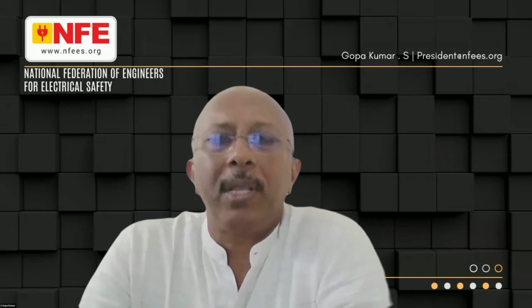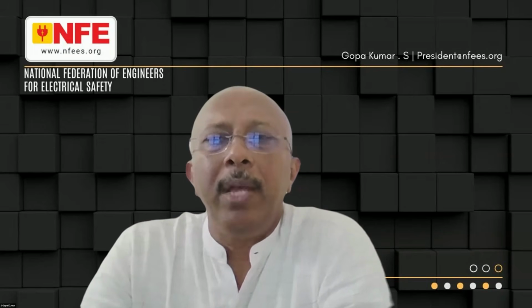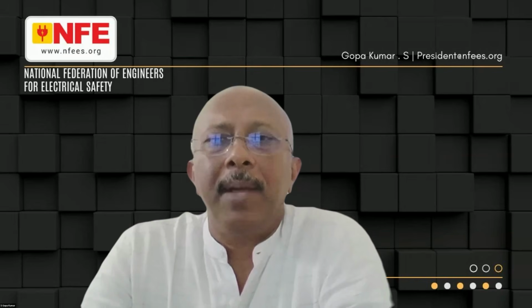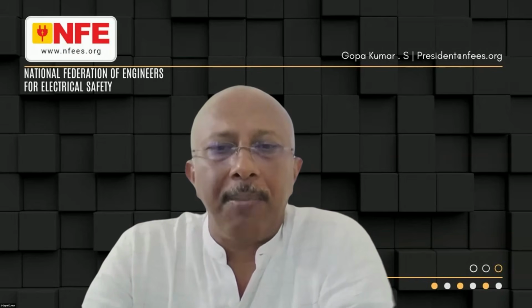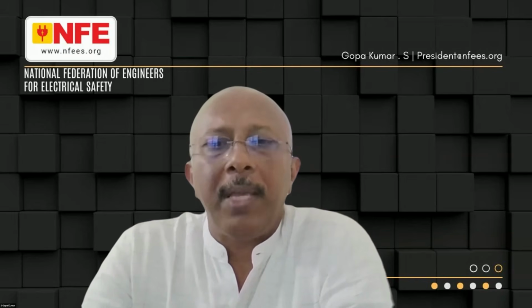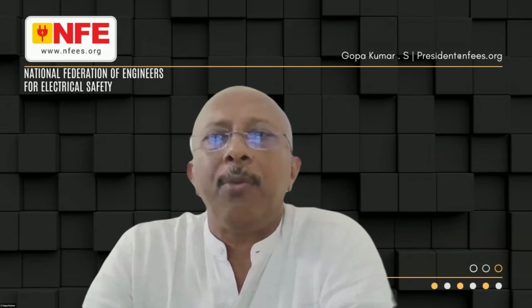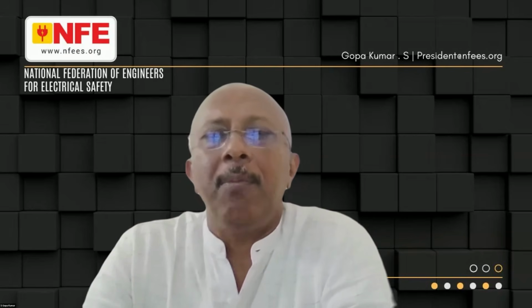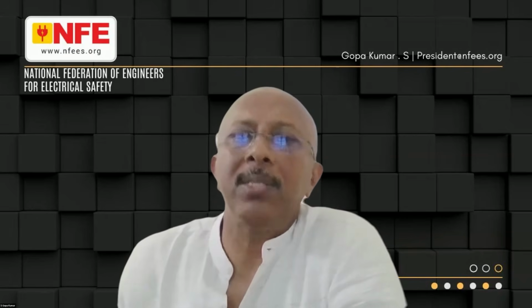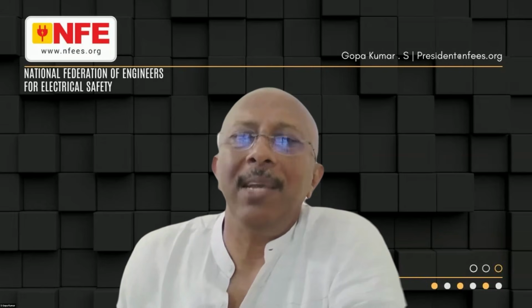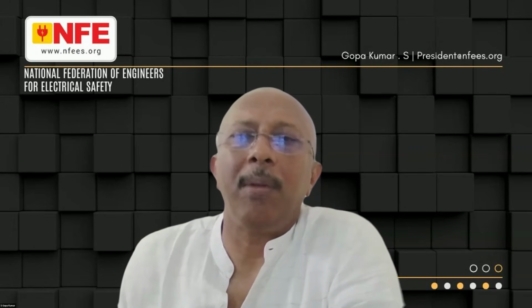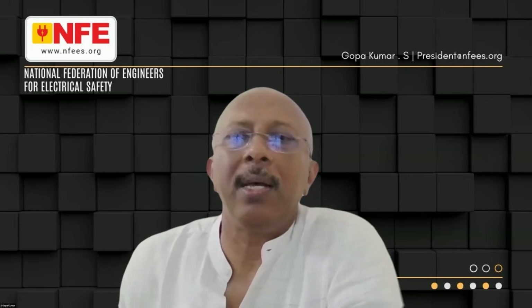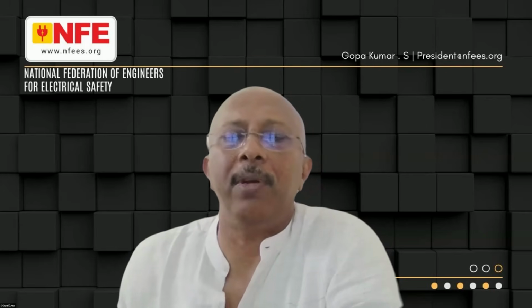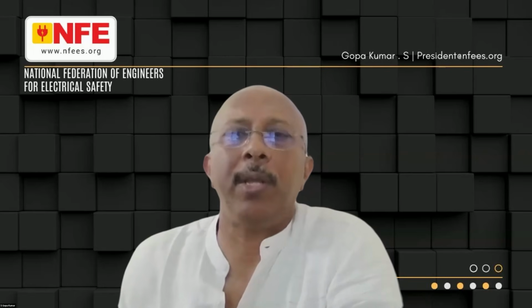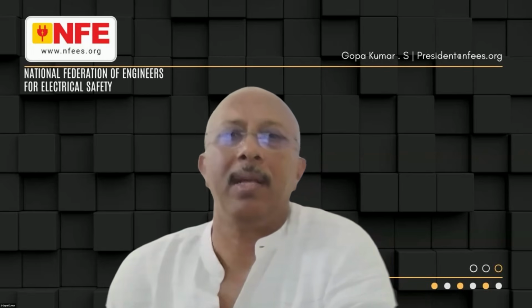Okay, this clean earth and power earth was the old name. The new name is functional earth and protective earth. Functional earth means the earthing arrangement you are making in order to ensure that the entire electrical and electronic equipment are working properly or functioning properly. Protective earth means in order to ensure safety of the electrical installation, you are making an earthing arrangement so that the entire electrical installation is safe. So safety earthing and functional earthing, or protective earthing and functional earthing, is the correct word.